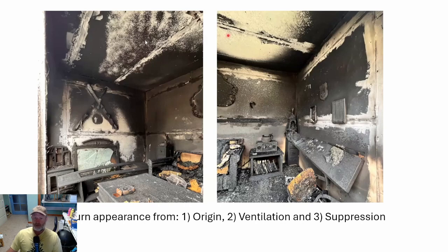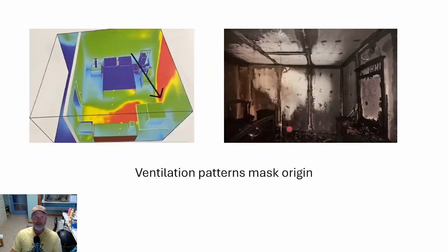But just looking at this, if you were looking at this, it'd be really hard to identify the origin from the clean burn patterns. You might think it's over here, but it was actually in the corner, as we previously noted. So, multiple tools have to be used in identifying the origin. A clean burn alone probably is not sufficient in this case.